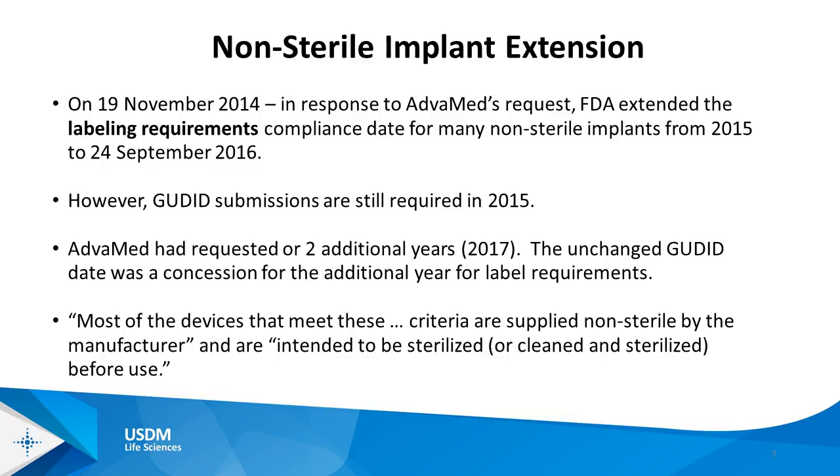Important to note, I think that AdvaMed had requested really 2 years, so to 2017, for all parts of the UDI requirements, and you can see that in fact FDA did not accept that. It gave them just 1 year, but kept the GUDID requirements as they were.